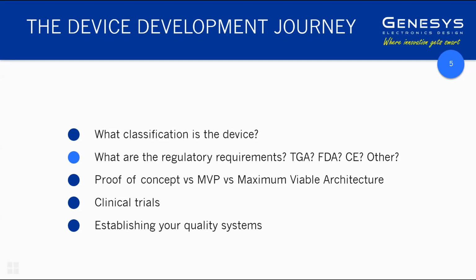They might have an idea of wanting to sell it to other customers, but what they don't realize is that in order to do that, they need to be what we call an ISO 13485 certified manufacturer of medical devices. To have this quality system established at your organization is a huge task, which again we'll leave for another webinar, but I just wanted to raise it now in this overview.